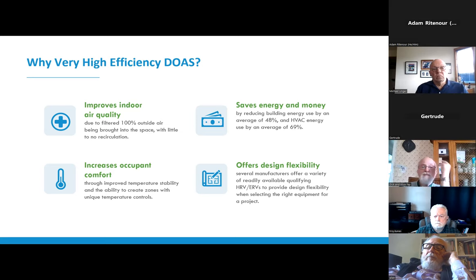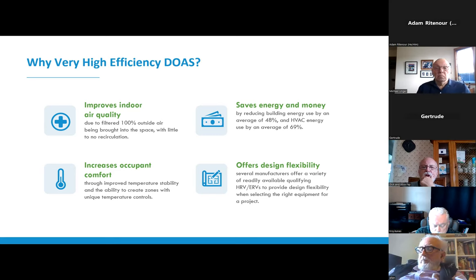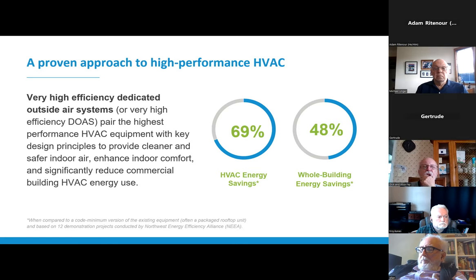Another reason we would choose VHE DOAS is because it increases occupant comfort. Zonal heating and cooling systems provide consistent indoor air temperatures across many diverse zones, and only when those zones are calling for it. And lastly, it offers design flexibility. There's a wide variety of ERVs and HRVs and heating and cooling units that meet VHE DOAS system design requirements. And it's really up to the freedom of a designer to pick the pieces that will best serve a building. I just want to highlight again that the big system benefit here is the reduction in energy use. That's on average 69% HVAC energy savings, and on average 48% whole building energy savings. And that comes from 12 of our 14 demonstration projects.